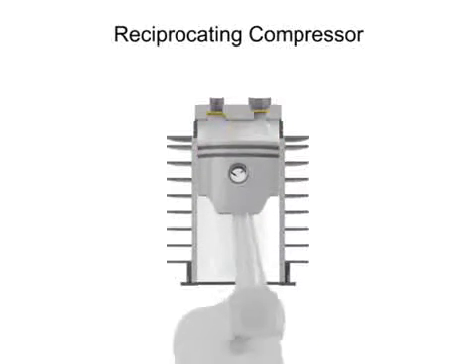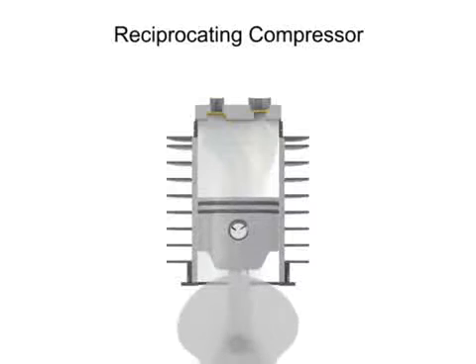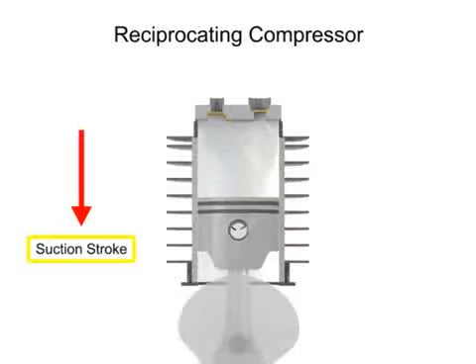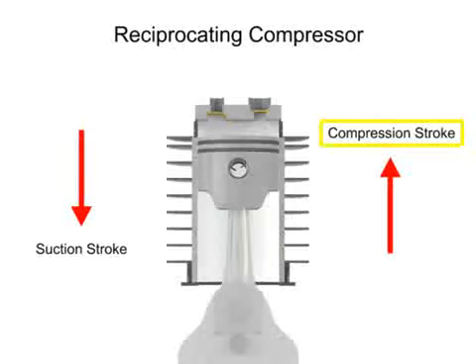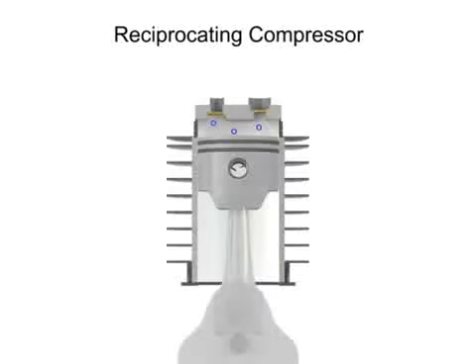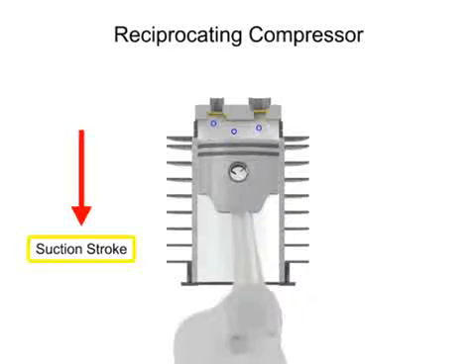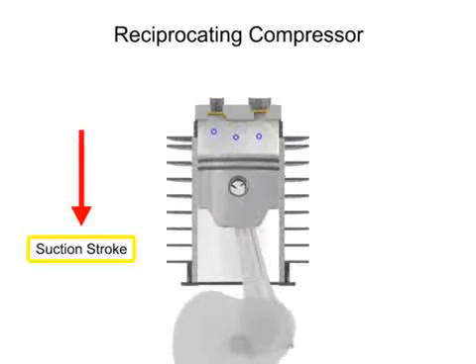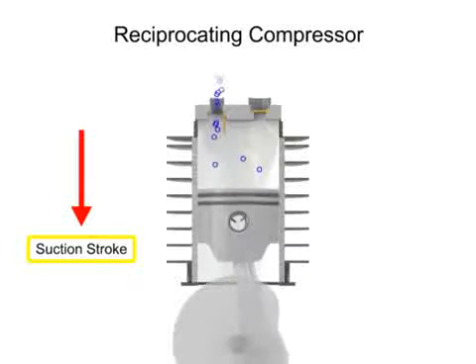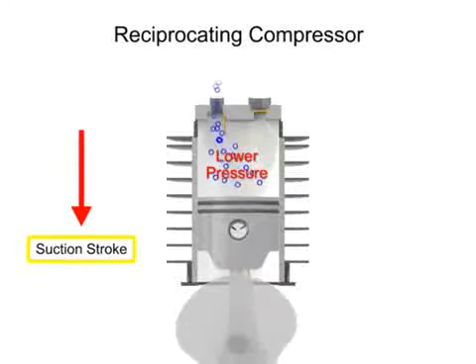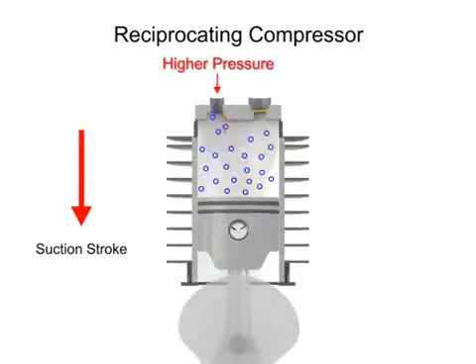The downward stroke of the piston is called the suction stroke. As the piston moves downward on its suction stroke, the volume increases within the cylinder. As the volume increases, the pressure within the cylinder becomes lower than the inlet air pressure. This allows the higher pressure outside air to push open the inlet valve and allow more air into the cylinder.